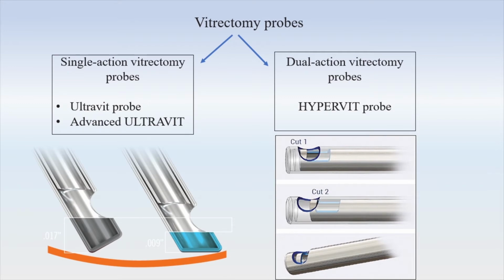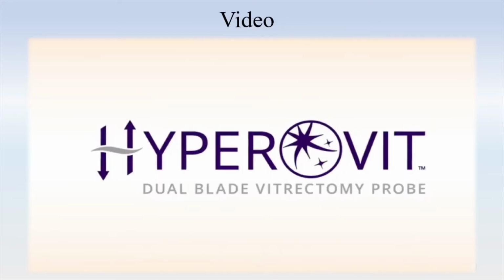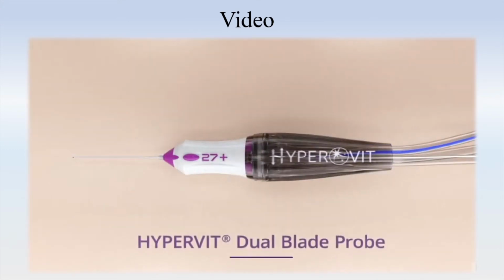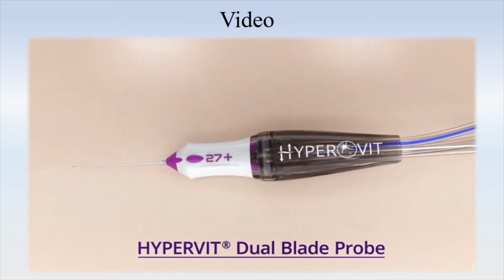Now, the main difference between the Hypervit and the Ultravit is that Hypervit has a two cutter, so it can cut vitreous twice. While moving forward, it makes one cut, and while moving back, it makes the second cut. And also, the duty cycle is always open. So this is a small video showing the difference between two cutters, Ultravit and Hypervit.